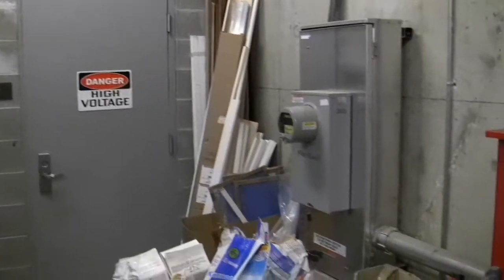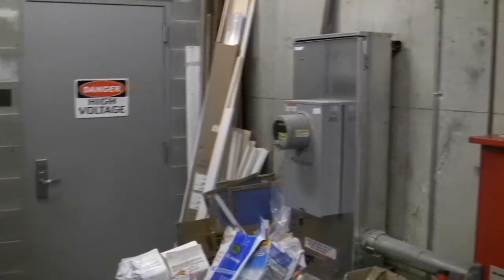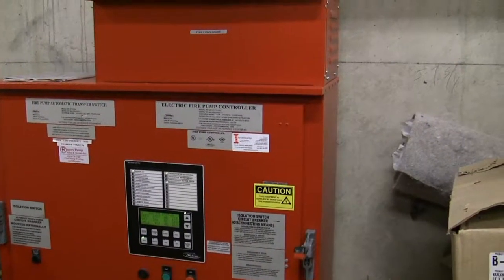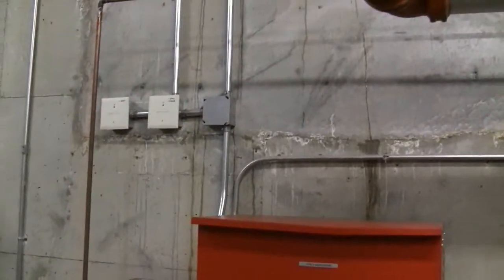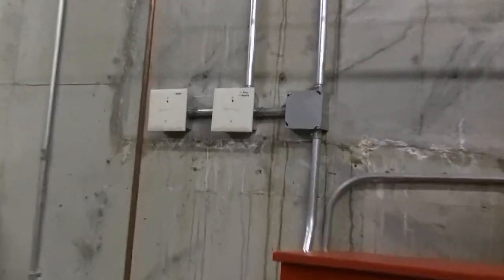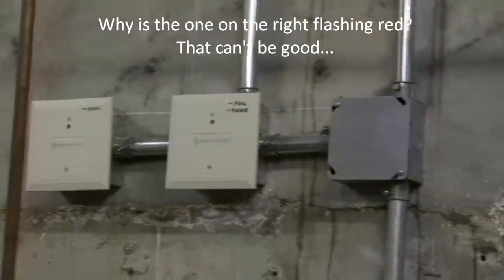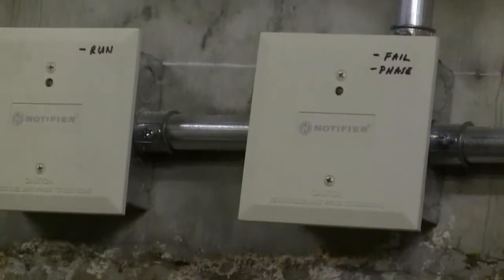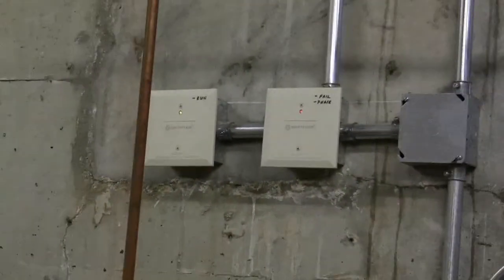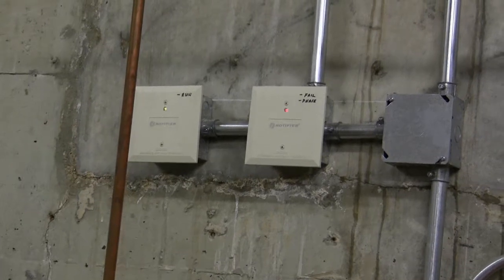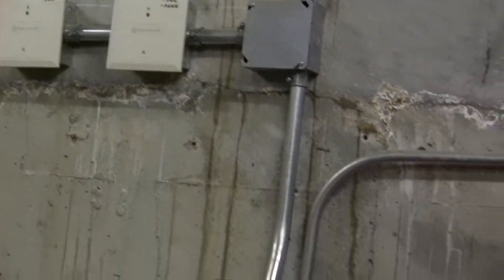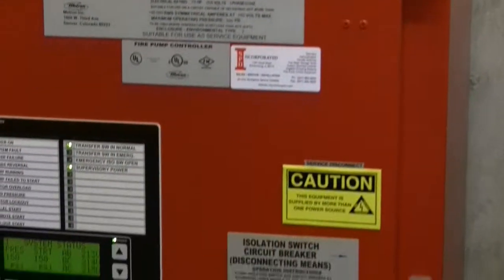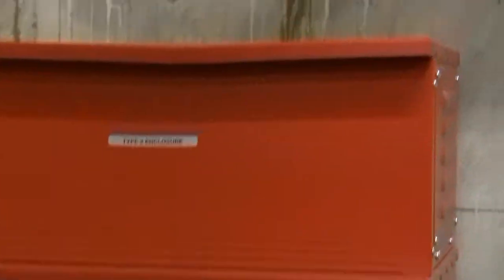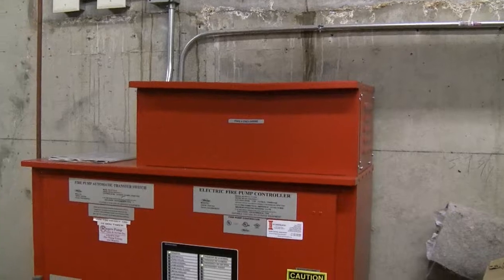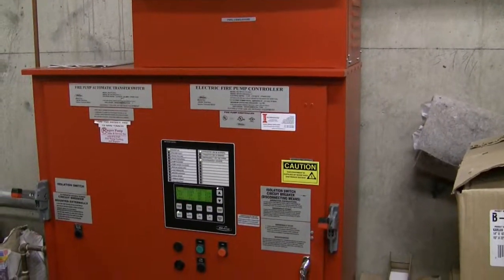But that's directly fed to this meter and then into this pump panel, which gives you a pretty good explanation as to what the system status is. Now, these flashing lights are sensors that are being read in the panel upstairs. Wherever you see these small flashing panels, that is a almost continuous polling read of all sensors: all of these valves that are wired, all the pump status, flow switches, pressure switches, valve tamper switches that are all part of the fire sprinkler system.